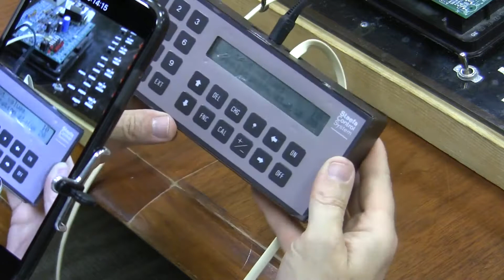Now, why would it be? I'm going to go to 0, 0. My zone temperature is 51, right? And we said my set point here was 72, 74 with the offset. So that makes sense that this particular card's gone to heating, right? So I'm going to go back out to the 10s, come back to where I was showing you. I go to that application status and hit enter. He's thinking that he's heating.